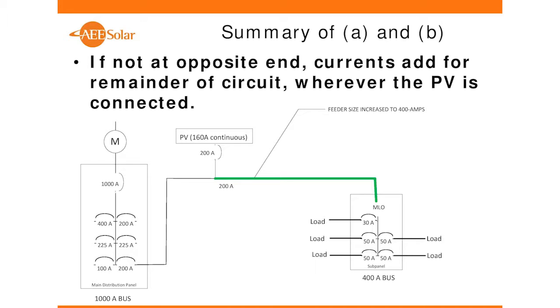It's either 200 amps from the utility or 200 amps from the PV or something in between. There is no way to get more than that. But this section of conductor here that's in green, which probably shouldn't be green, it should be red, is going to be, in order for this to work, you'd have to have a 400 amp bus and you'd have to have a 400 amp conductor. Okay, the probability of that's really small, but that would be one way to address it, would be to upsize those downstream conductors. Okay, so that's A. That would be complying with A, is to upscale this to 400 amps and have a 400 amp panel.